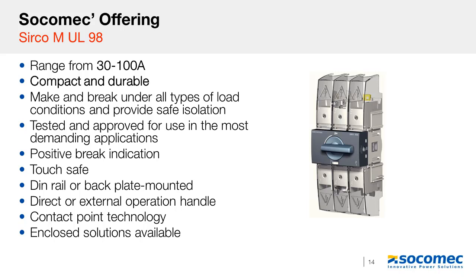We also offer the Socomec range that is UL98 certified. You can see on the right of the slide that the switch is a little bit bigger. It has more distance between the poles, with those terminal shrouds, things like that. This ranges from 30 to 100 amps, so really for smaller UL98 applications, lower rating ones. And again, this is customizable with our large range of accessories. You can see that it's just a little bit bigger, but that's due to the higher short circuit rating requirements, the higher overload withstands, and the larger spacing that the UL98 standard requires for these kinds of switches.